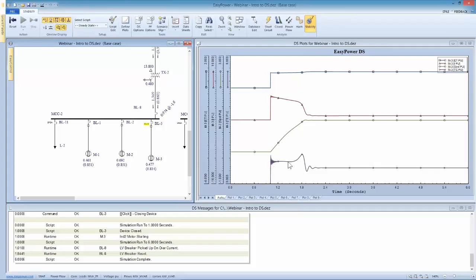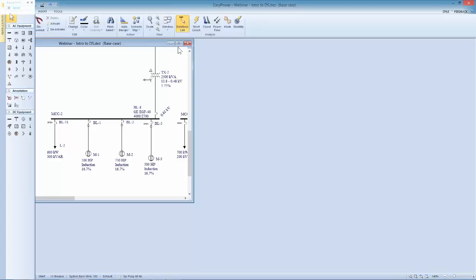Now you can see here that we go for 1 second at stable operation, and then we start the motor, and the motor looks like it's up to speed right at about 2 seconds, which means we have a 1 second start time.